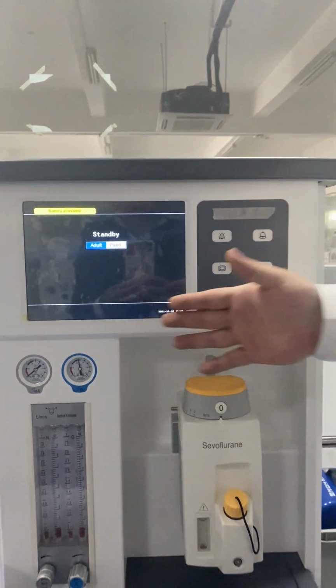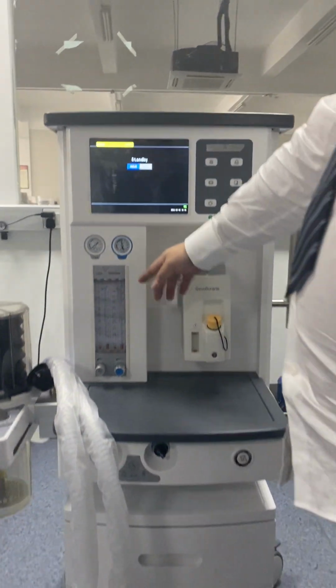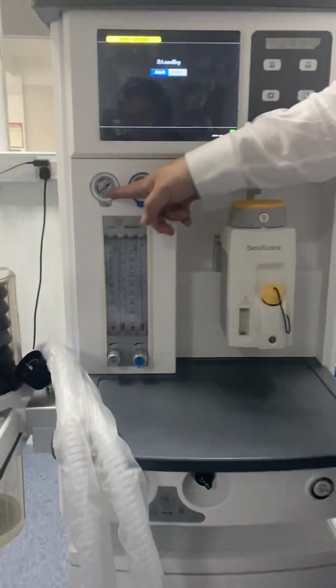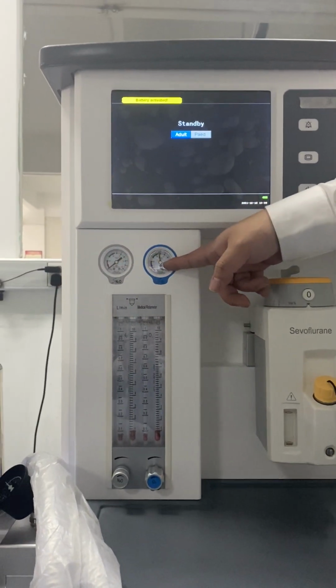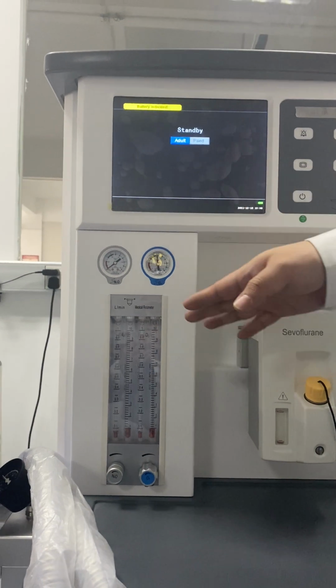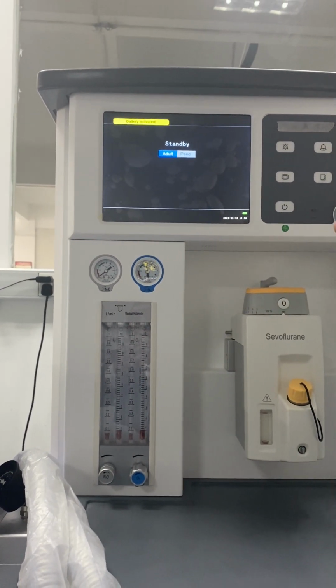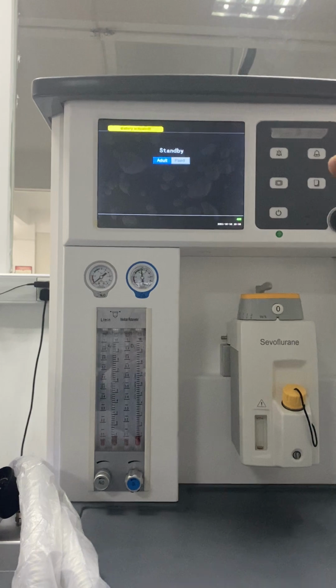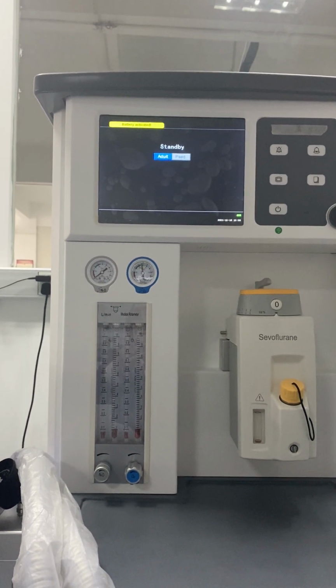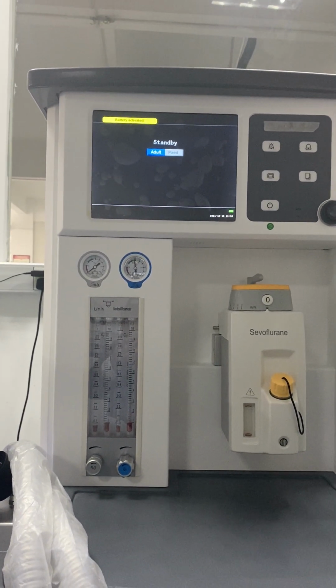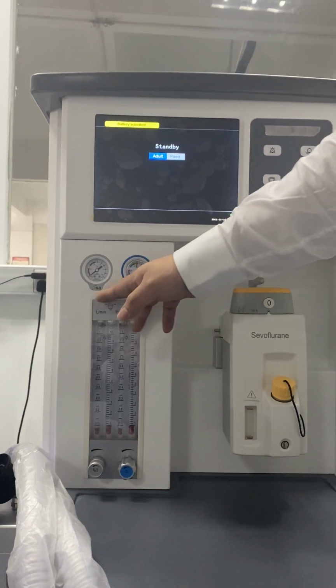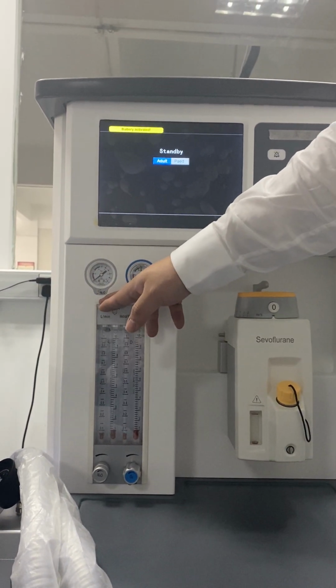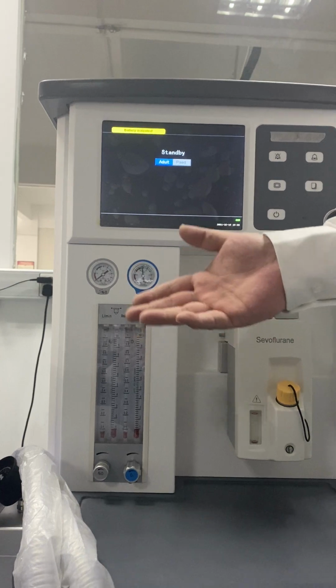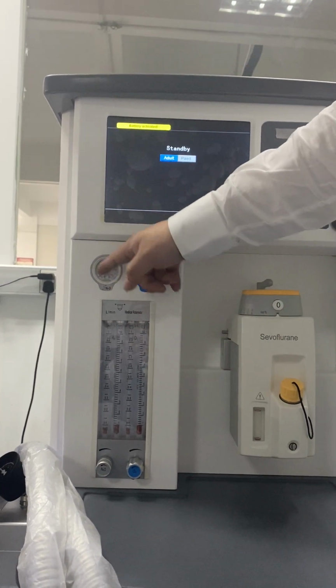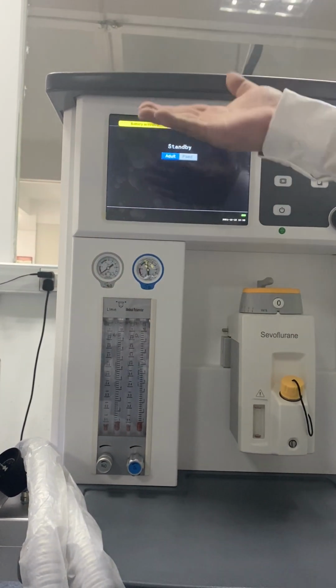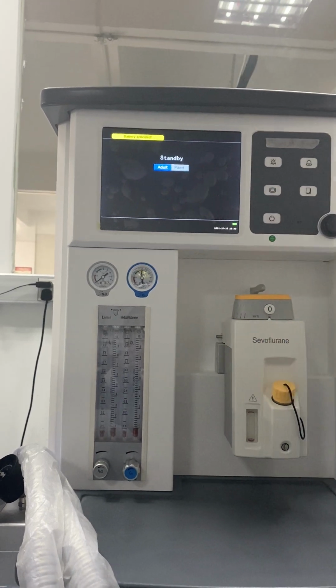And then we will introduce the lower side here. You can see here we have 2 gauges, a pressure gauge and also the flow meter. This machine is actually a 2-gas system. So oxygen is the driven gas, so we must have the oxygen. Then between nitrous oxide and air, you can choose one of them. For this machine here it is labeled oxygen and nitrous oxide. And if you don't want to use nitrous oxide and want to use air, then we can change here to air. And also at the back side of the machine, you can connect with the air source.